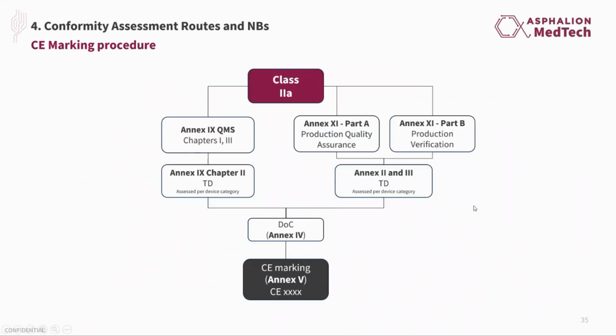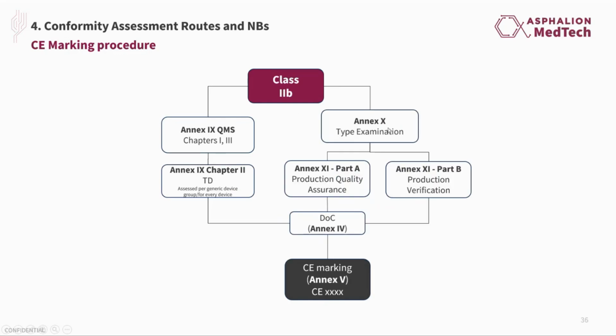Okay, then we go with Class 2A devices, and there's the option to go through the technical documentation and the QMS according to Annex 9 and then Annex 11 Part A or Part B, because Annex 10 and Annex 11 are specifically for devices classified as Class 2B and Class 3, but there are in Annex 11 some specific exceptions for Class 2A devices. So going to Class 2B devices, we have the following. We can go through Annex 9 with the QMS and the technical documentation, and there is also the possibility of going through Annex 11.